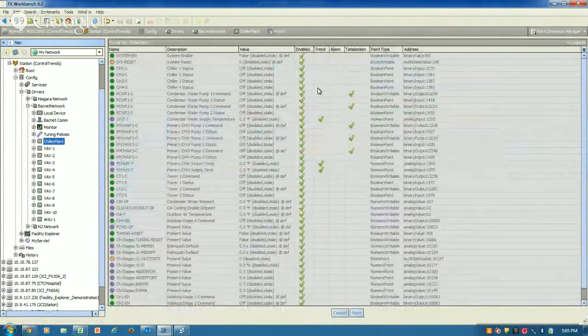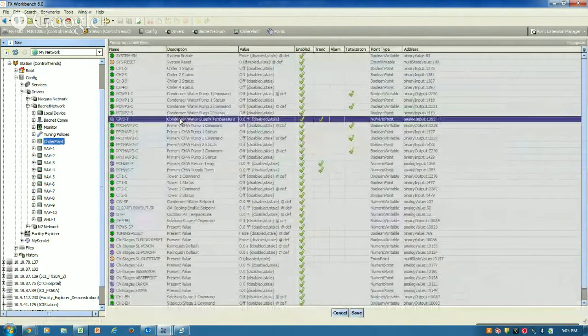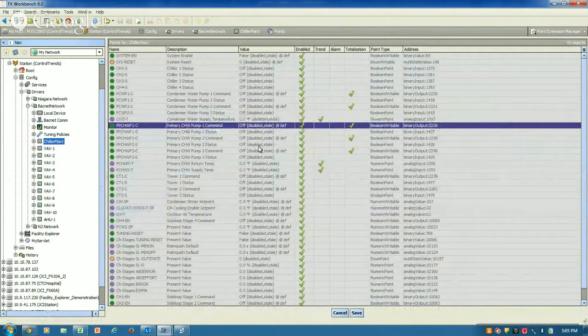It automatically added some extensions on points right here. So let's say it came as a default and it's trending my condenser water supply temperature. But let's say I wanted to trend my primary chilled water pump 1 command. In order to add trends onto this, all I have to do is check a box and do a change of value or an interval. I want this thing every time it changes value to put a trend on there. I've automatically added a trend.